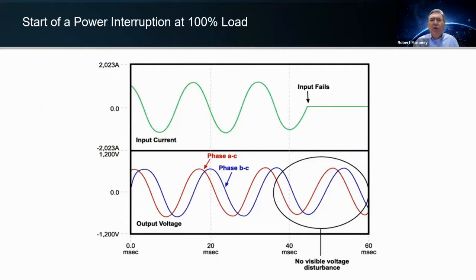This shows an input failure of the energy source from the utility. And as you can see, there's no visible voltage deviation as we transition from utility energy over to UPS energy. And we go into discharge, then making the transfer over to an alternative energy supply.